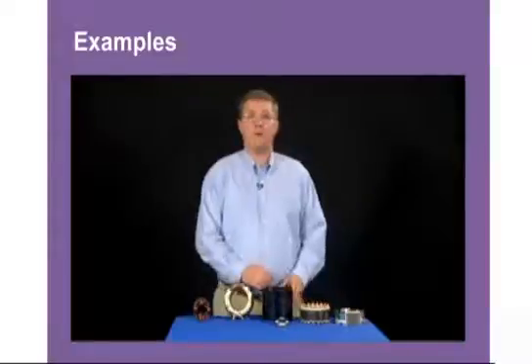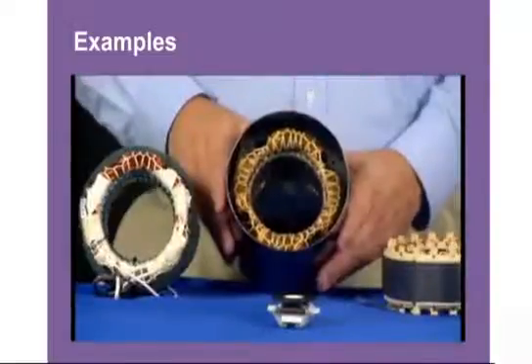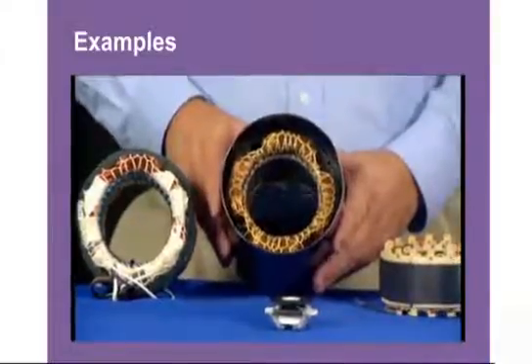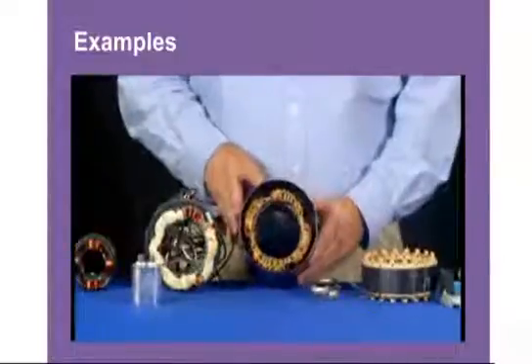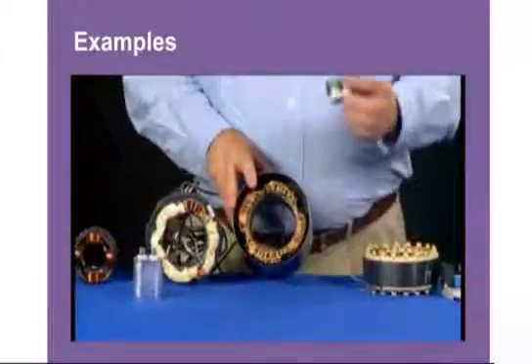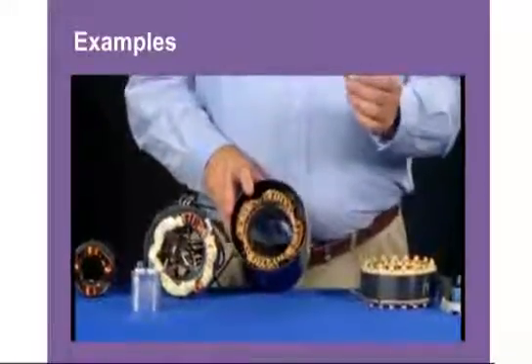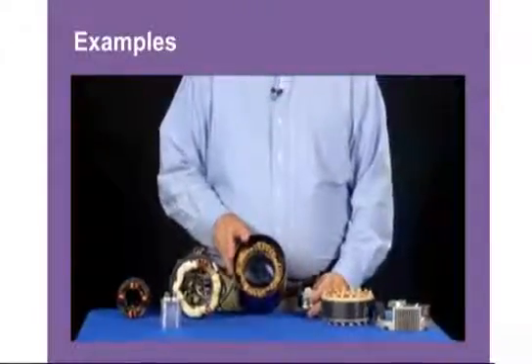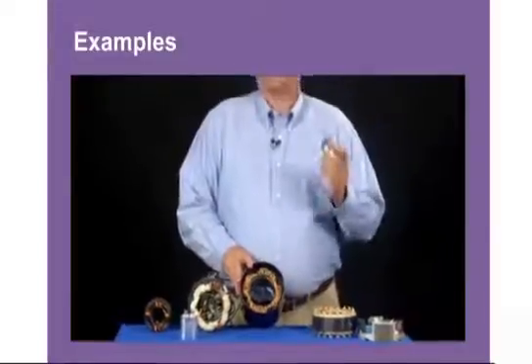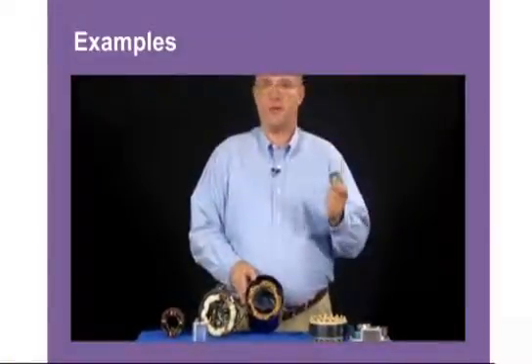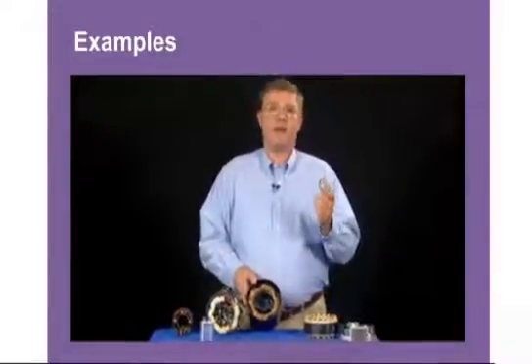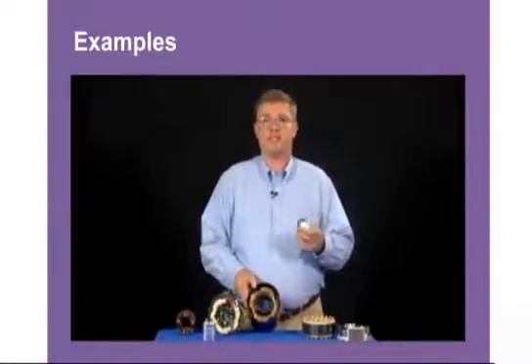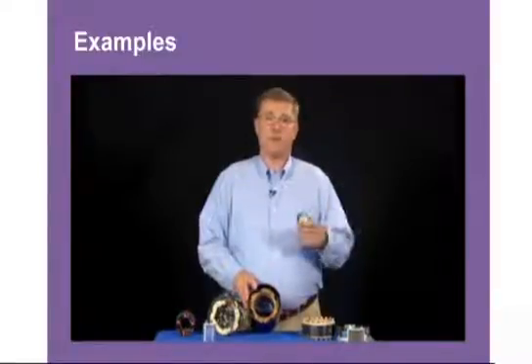The next type of motor we talk about are split phase motors. This type of motor also has two windings — an auxiliary start winding and a run winding. What makes split phase motors unique is a centrifugal switch. This switch allows the motor to start on the auxiliary winding, which is a very fine gauge wire, designed to slowly come up to speed until centrifugal force opens the switch and allows it to go to the run winding. A typical belt drive application allows it not to take off immediately and throw the belt off the line.